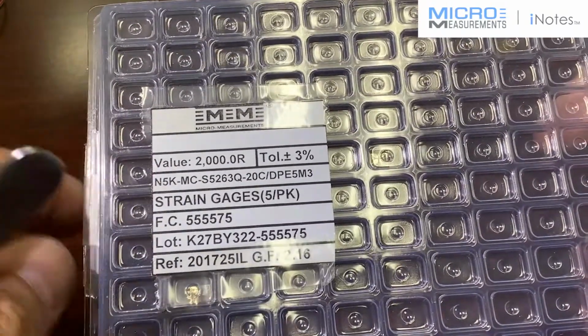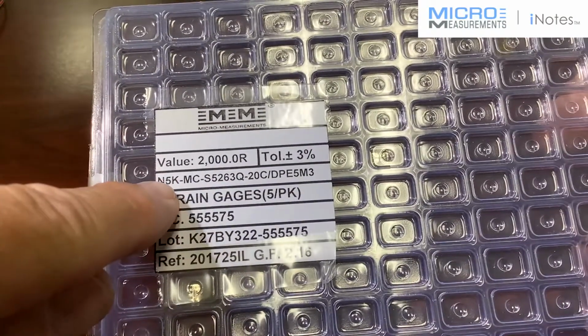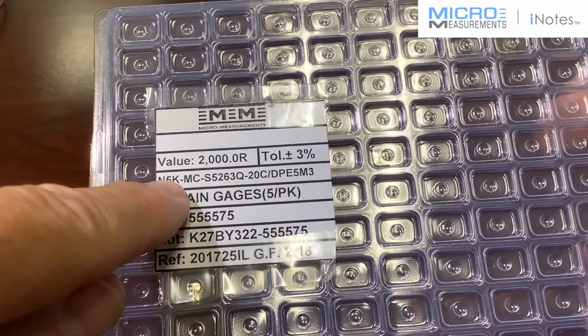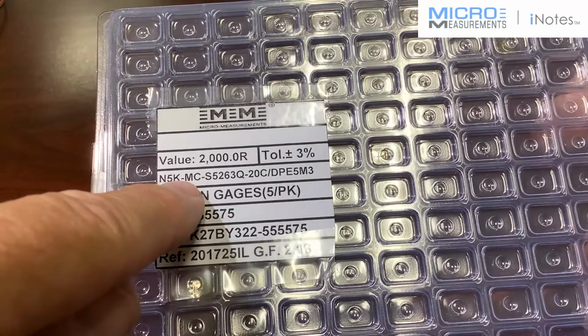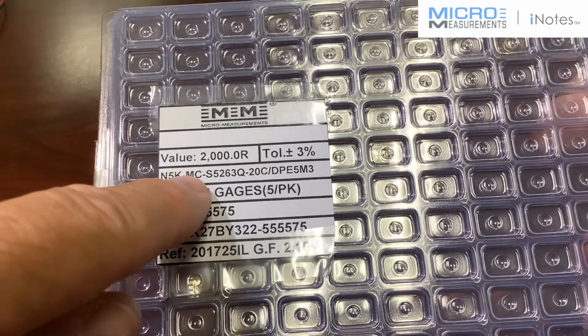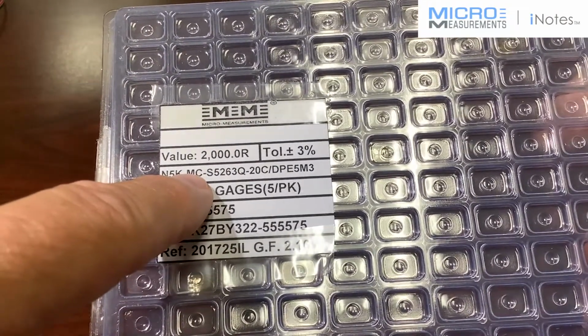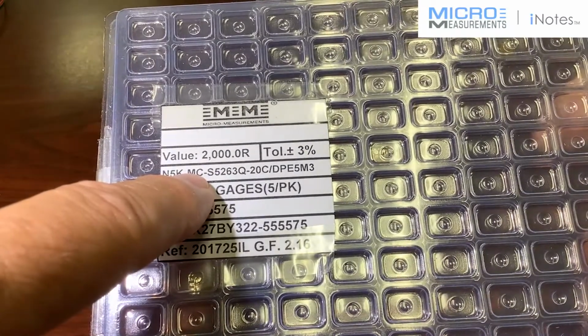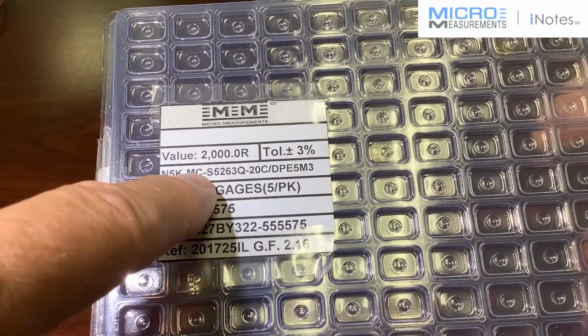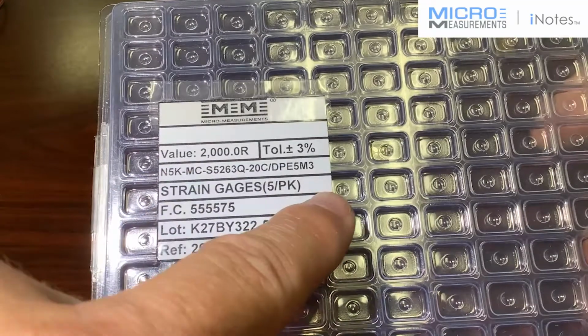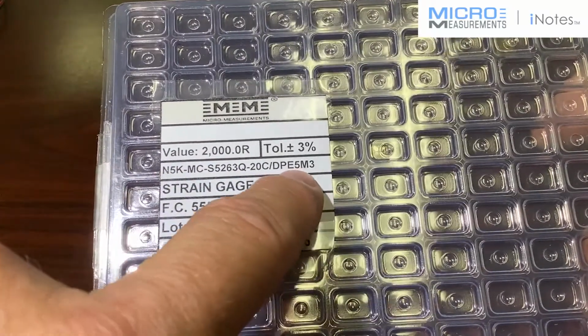Basically, that means it's an N5K construction, which is associated with a higher temperature. The MC means it's modulus compensated, one of the options we can add to strain gauges where we adjust the foil so that it matches a modulus variation of your material. This particular mod comp happens to be an M3.